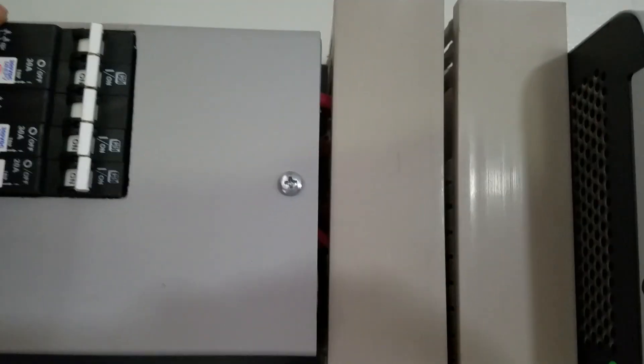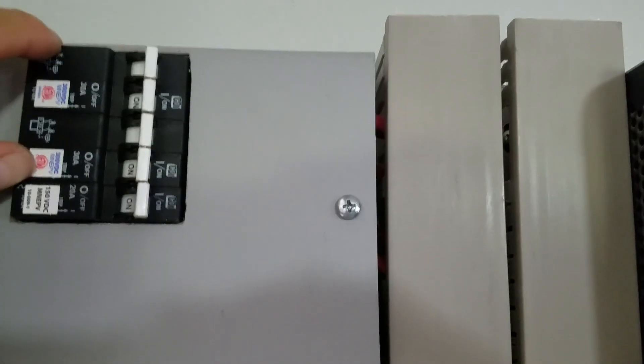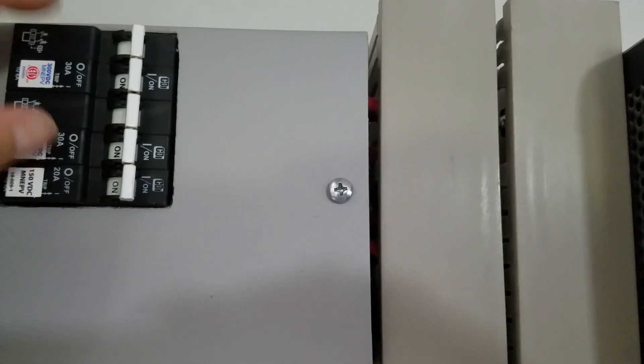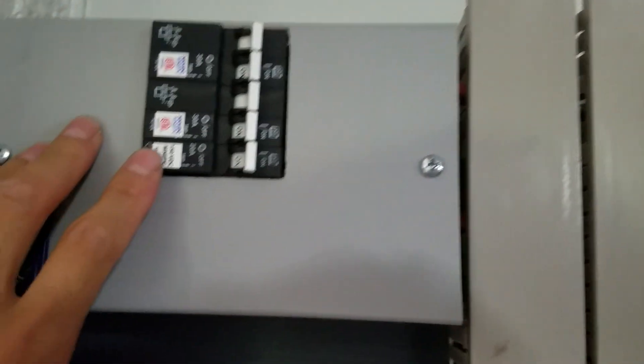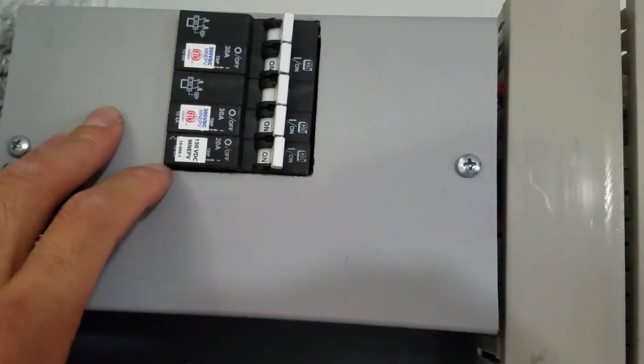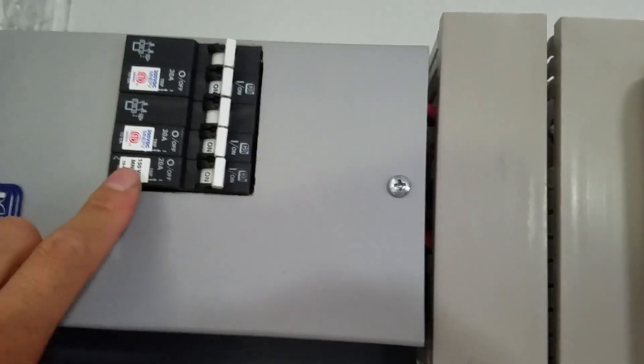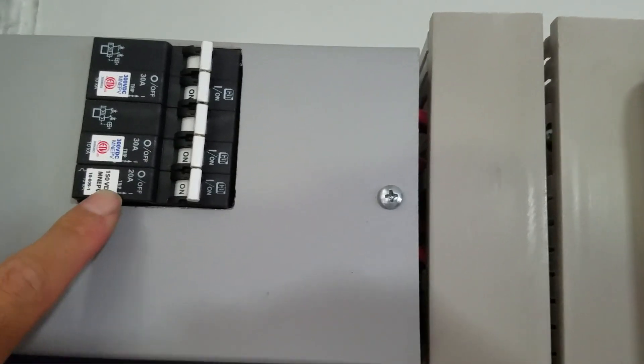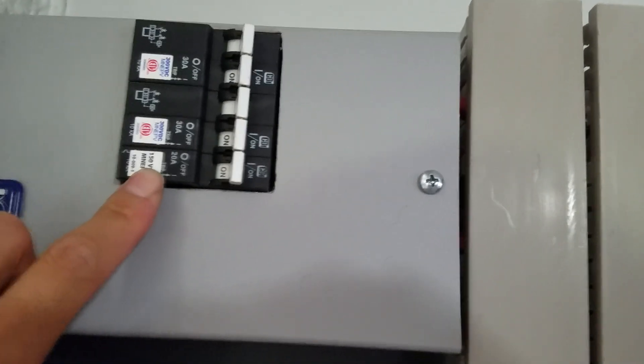First thing I did was I modified this Midnight box. Stock, you only have four slots for the breakers, and two of them are for the two big arrays that come into this MPP. There wasn't a slot, so I had to cut that out and add another slot so I can put the PV shutoff for the Midnight.